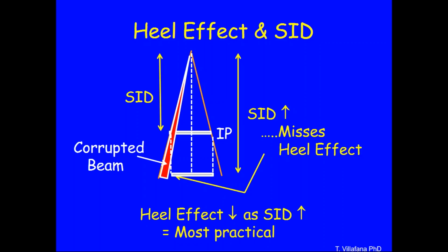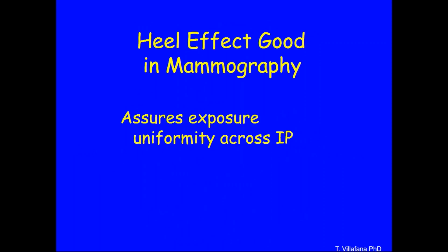Okay. Now, I've painted this heel effect as the bad guy, right? We don't want heel effect. We do anything we can to eliminate heel effect. But there's a very special condition in mammography where we love heel effect. We go out of our way to make sure that we have heel effect.